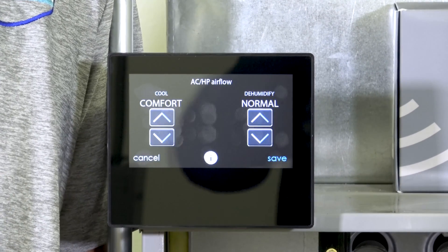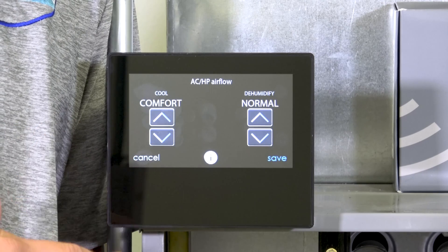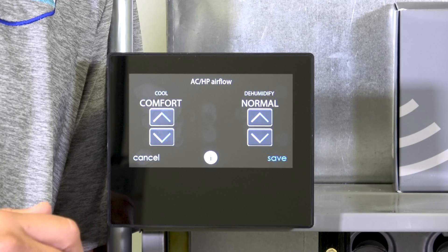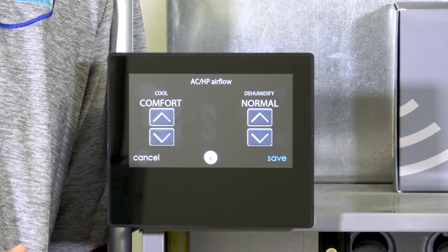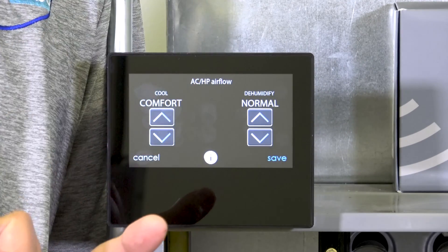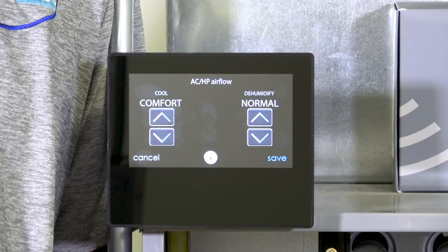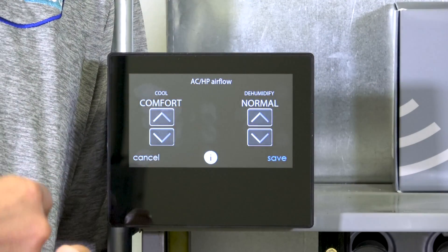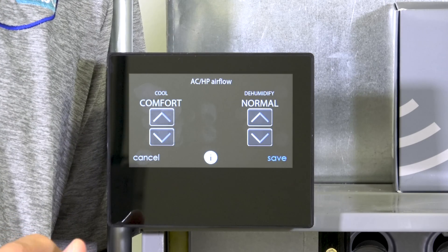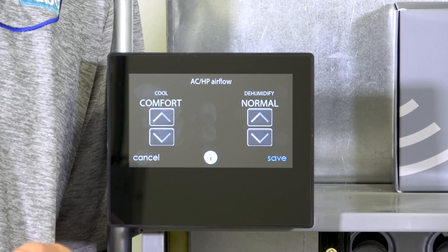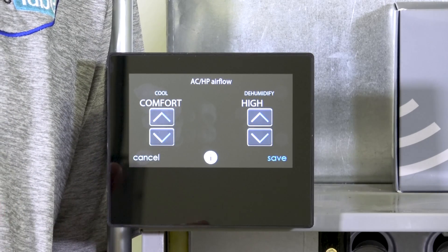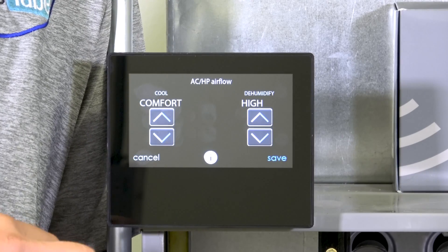For dehumidification, choices are Normal and High. Normally you'd leave it on Normal. In dehumidification mode the thermostat calls for the compressor on one of the lowest stages available even without a cooling need — the goal is to slow the airflow through the evaporator coil so air stays in contact longer and pulls more moisture out. If your ducts are uninsulated in an attic they might sweat at low speed — the proper fix is to insulate them, but if not you can bandaid it by selecting High airflow in dehumidification mode. It's a compromise: you still get some dehumidification, just less.